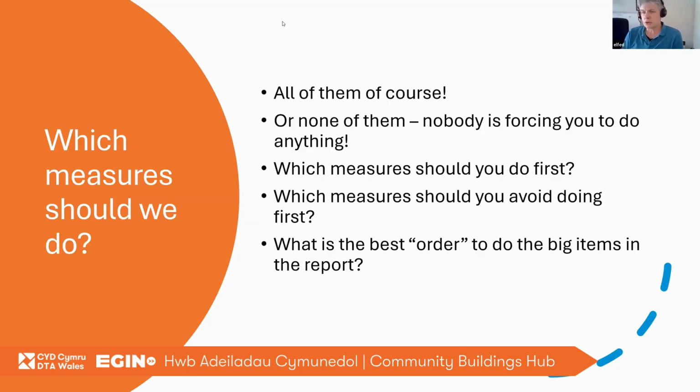And the other thing as well is, you size the heating system for the heat lost out of the building. So if you install the heating system first, your building might have an energy loss of 20 kilowatt peak. So you'd have a 20 to 25 kilowatt boiler. If you insulated the building fully, maybe the heat demand would go down to 10 kilowatts. So now your boiler is twice as big and twice as expensive as it would need to have been.